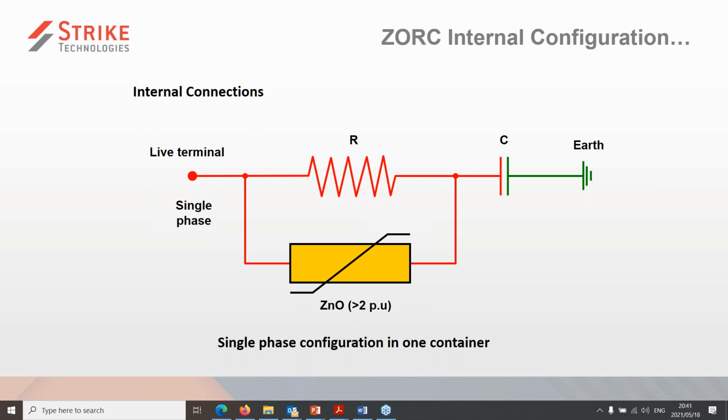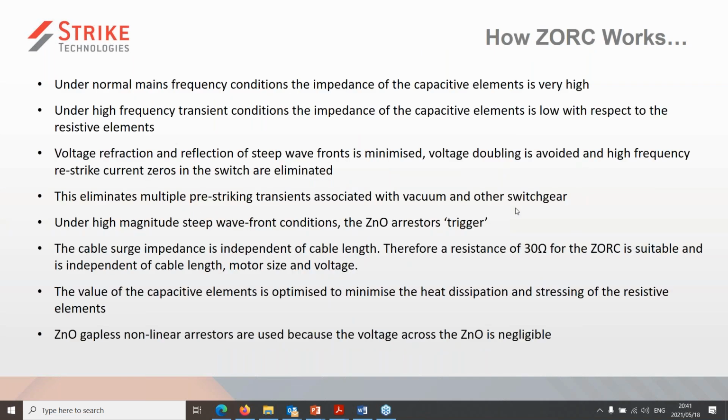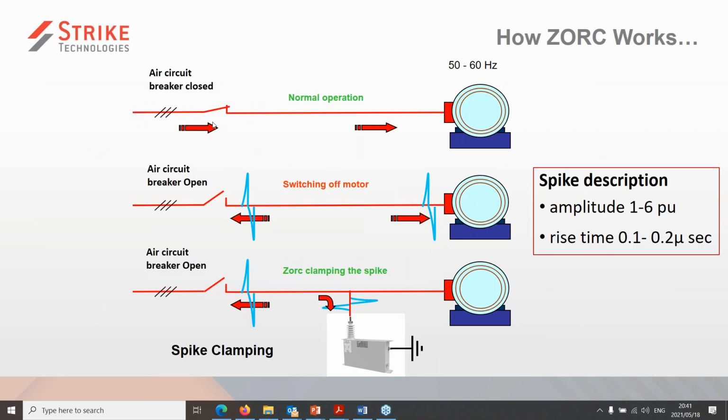Very simply then, that's how you would calculate what your per unit value is in the system where ZORC is being applied. Right, so this slide just describes exactly what I've explained as to the functionality of a ZORC. This graphic shows you very simply the opening and the closing of the VCB, where the transient is generated, goes to the motor terminals and bounces back.